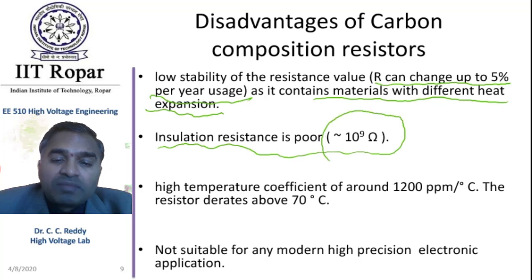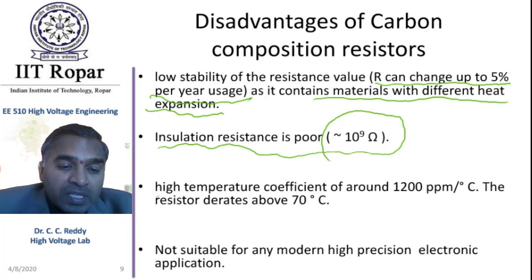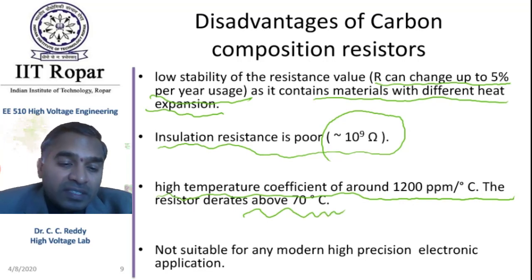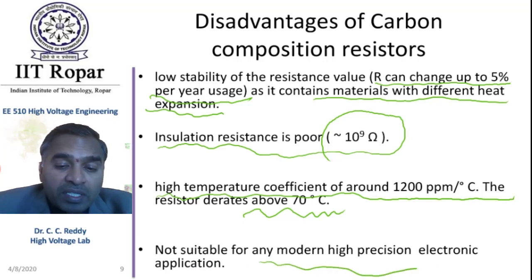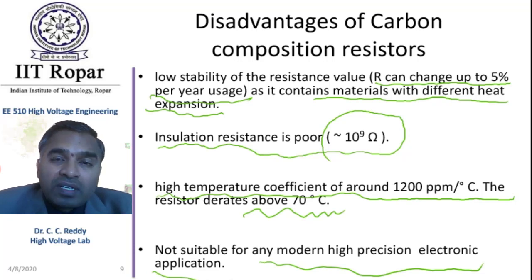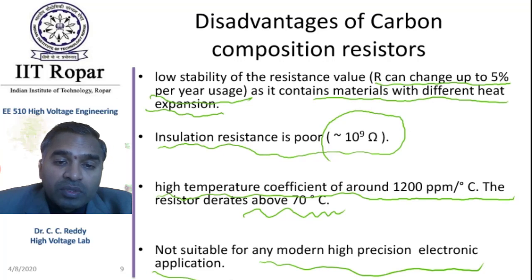Insulation resistance is actually poor — 10 to the power of 9 ohms — so achieving higher resistances is difficult. One more problem is a high temperature coefficient of around 1200 ppm per degree centigrade, and beyond 70 degrees centigrade it gets derated. So these resistors are not suitable for high precision electronic applications. But for electrical high voltage applications, we are mainly concerned about self-inductance, self-capacitance, and high energy capacity — which is very important compared to wire wound — and that is one thing in favor of carbon composition resistors.